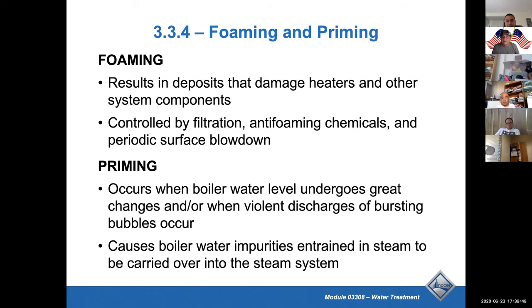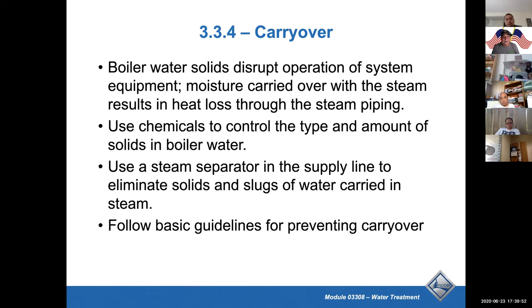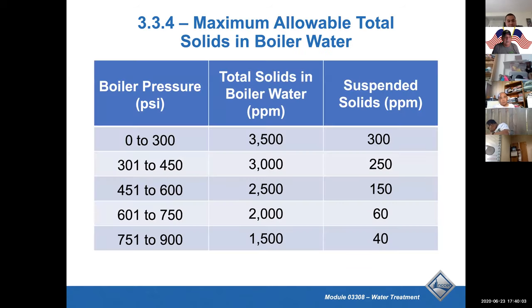Foaming. Priming. Wow, there's a lot of boiler water here. Use chemicals to prevent it, or use a steam separator. Maximal total solids: if it's 0 to 300 pounds, it's 3,500, with suspended solids at 300. Then you go all the way up to 1,540. So the higher the pressure, the lower your suspended solids and total solids.